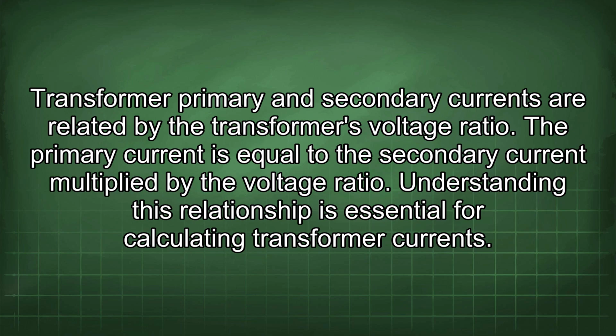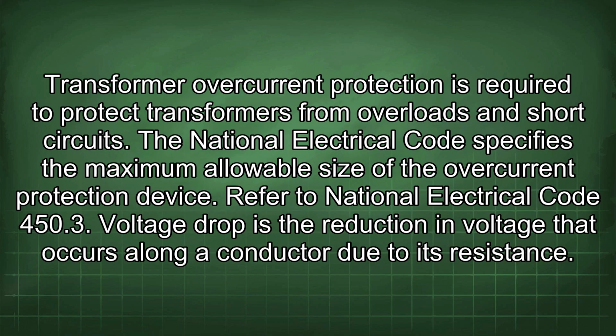The primary current is equal to the secondary current multiplied by the voltage ratio. Understanding this relationship is essential for calculating transformer currents. Transformer overcurrent protection is required to protect transformers from overloads and short circuits. The National Electrical Code specifies the maximum allowable size of the overcurrent protection device. Refer to National Electrical Code 450.3.